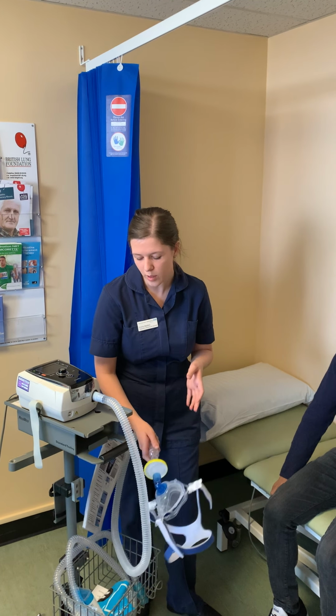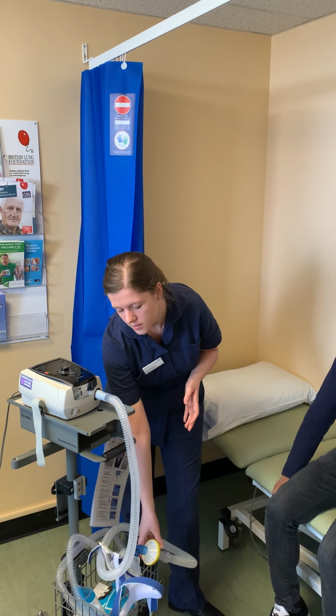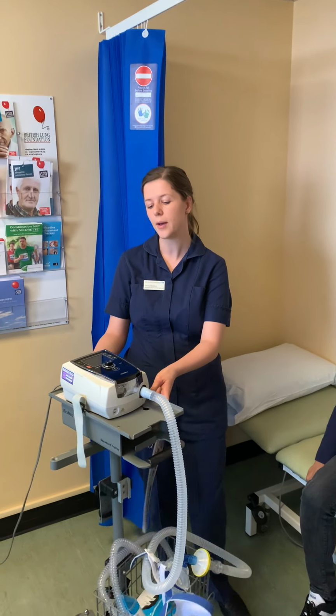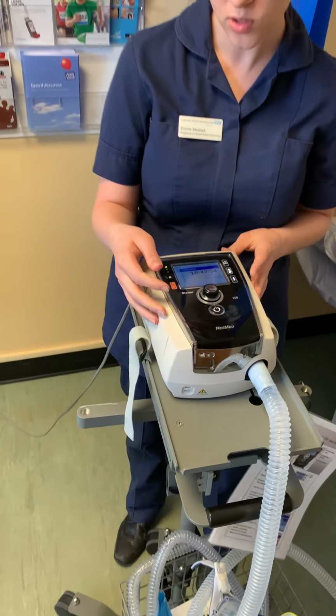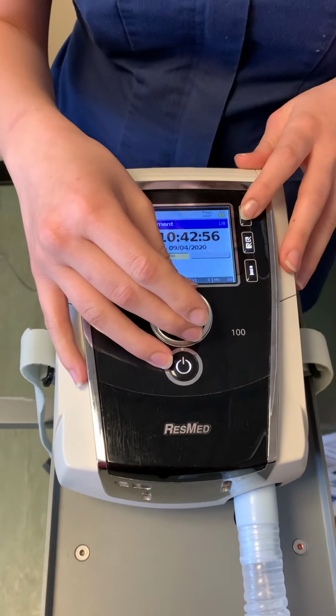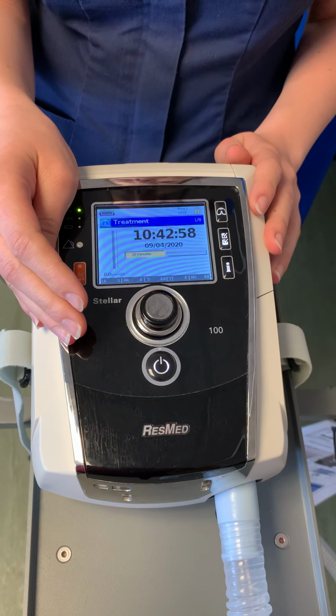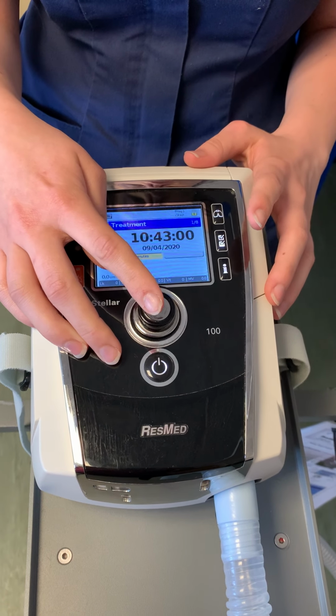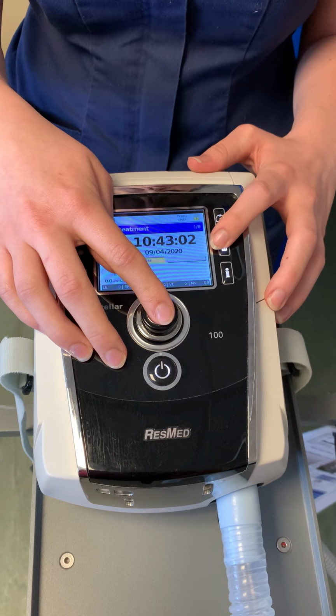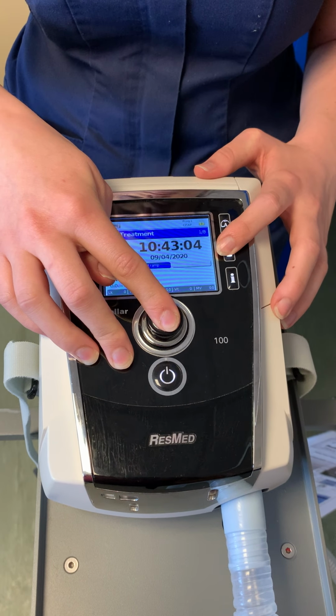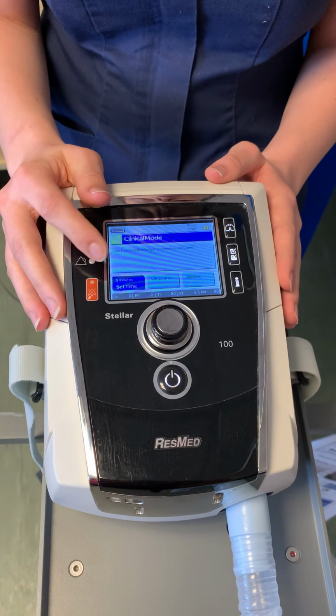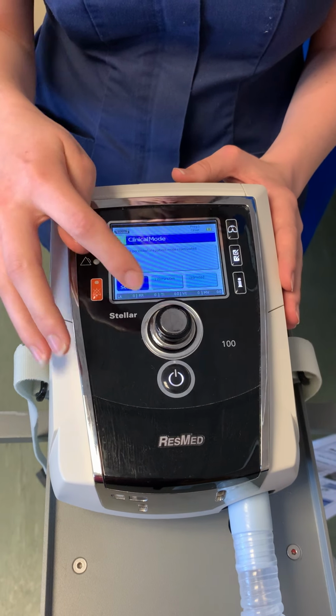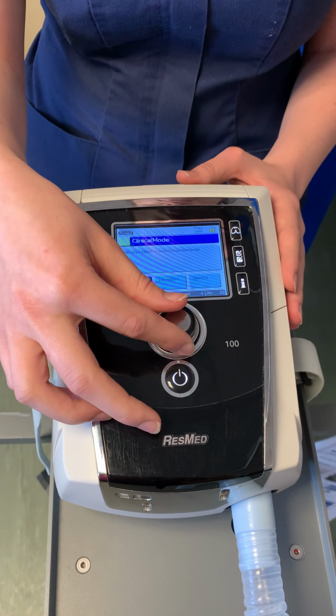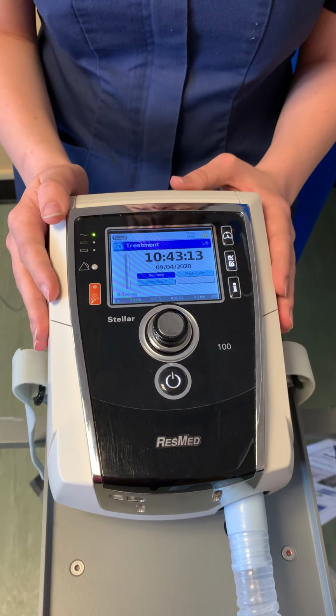So first of all, we've turned the machine on. Now I'm going to show you how to do your learn circuit. A learn circuit is really important because it enables us to check that the machine is safe. First, you come to this screen and you're going to unlock. You press the middle button and the 2 ticks and hold down for 3 seconds. It's really good to make sure you only unlock for 5 minutes, so that the machine locks again and is safe, and no one can adjust your settings.